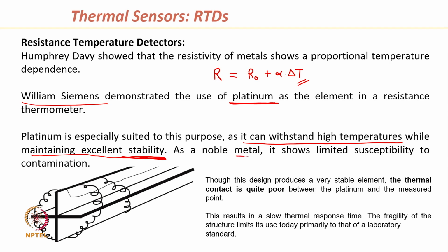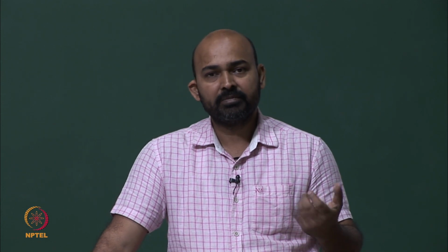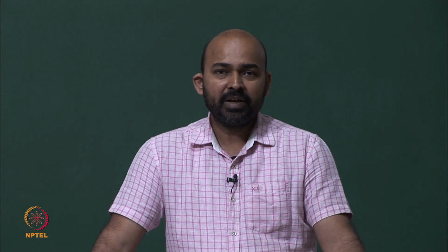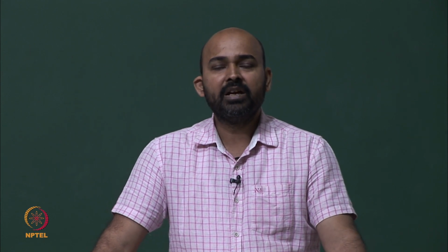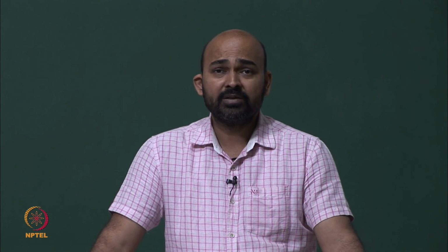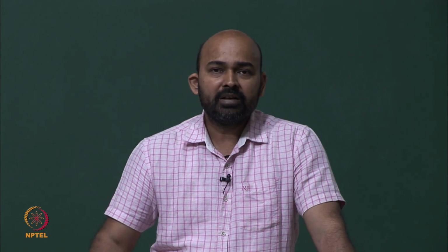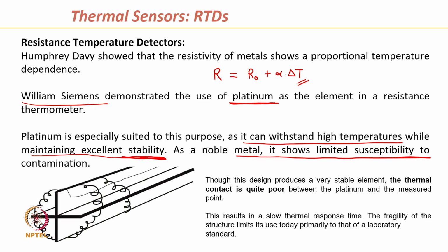As a noble metal, it shows limited susceptibility to contamination. You can put this platinum inside a chamber which is filled with some gas or some reactive liquid. The platinum does not react with the environment or that particular gas or liquid, and it does not contaminate the fluid inside. So, platinum is a very noble material to use as an RTD. Though this design produces a very stable element, the thermal contact is very poor.